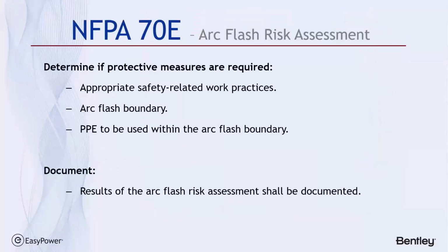Okay, so the arc flash risk assessments determine the protective measures that may be required, what the arc flash boundary is, and what PPE should be used. All of this should be documented in the arc flash risk assessment documentation, which includes the data that was collected, the trip times available in any protective devices, and any elevated incident energy that requires mitigation if possible. Again, the more complete the documentation, the better it can be utilized by safety personnel and maintenance people working on the equipment.